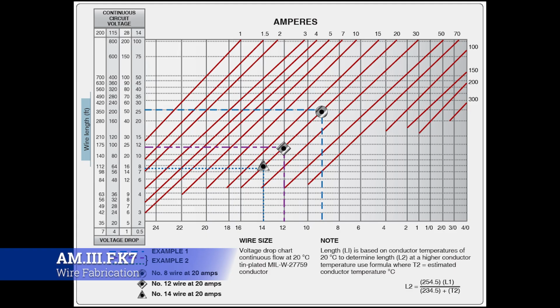We also want to prevent overheating while carrying the required current. Voltage drop very rarely is going to be a systemic problem that you see. You will see voltage drop problems because of faults in the wire, but not just because the wrong wire is selected. However, whenever you see repair work that's not following engineering guidelines or specifications, you'll see people install too small a wire for too big a load, and what happens is it gets hot, and it either melts the insulation, discolors it or the things around it, or it straight up starts a fire. So we want to prevent those two things by selecting the correct wire for the correct job.